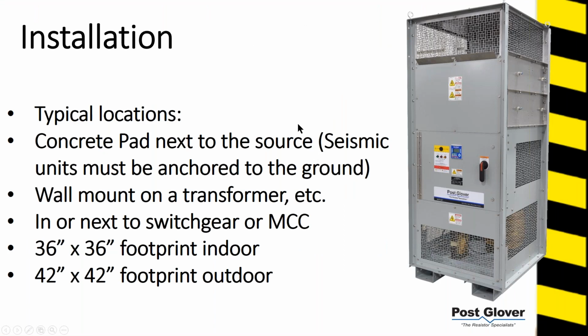In terms of installation, typical locations, you get a concrete pad next to the source. If you have a seismic unit, it needs to be anchored to the ground. We do have some seismic units. They're not this. These are our fully continuously monitored HRG systems for continuous operation. These are actually 36 by 36. You see this footprint indoor right here.